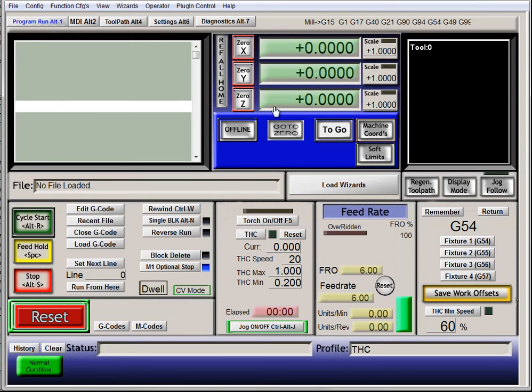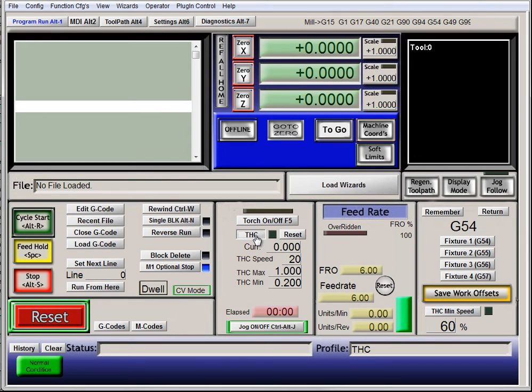Right now, we want to be able to see the ZDRO responding and doing stuff, and it's not. The reason is, we have to enable THC mode for it to respond to the signals to tell it to go up and down.